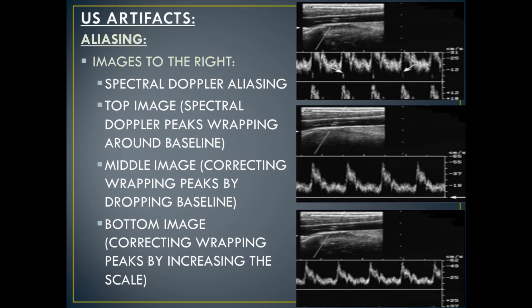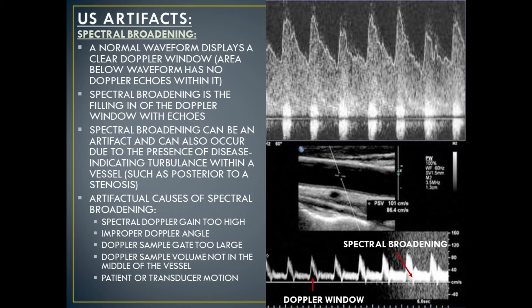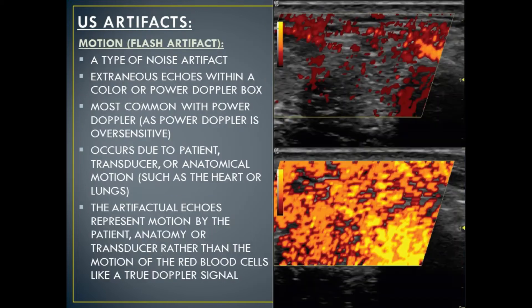Dropping the baseline and increasing the scale or the PRF are two techniques to eliminate artifactual spectral Doppler aliasing. The next type of ultrasound Doppler artifact is known as spectral broadening. On ultrasound, a normal spectral Doppler waveform displays a clear Doppler window — the area below the waveform that has no Doppler echoes within it. Spectral broadening is the filling in of the Doppler window with echoes. Spectral broadening can be an artifact, and can also occur due to the presence of disease, indicating turbulence within a vessel such as posterior to a stenosis. Artifactual causes of spectral broadening include the spectral Doppler gain being too high, improper Doppler angle, the Doppler sample gate being too large, the Doppler sample volume not in the middle of the vessel, or due to patient or transducer motion.